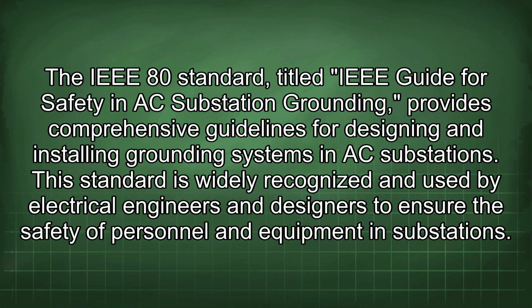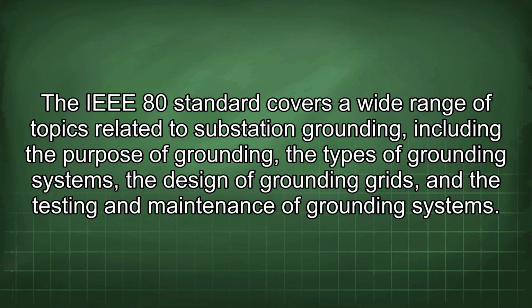The IEEE standard, titled IEEE Guide for Safety in AC Substation Grounding, provides comprehensive guidelines for designing and installing grounding systems in AC substations. This standard is widely recognized and used by electrical engineers and designers to ensure the safety of personnel and equipment in substations. The IEEE standard covers a wide range of topics related to substation grounding, including the purpose of grounding, the types of grounding systems, the design of grounding grids, and the testing and maintenance of grounding systems.